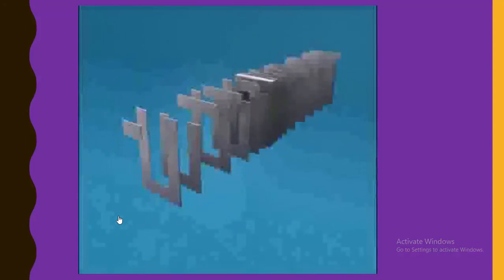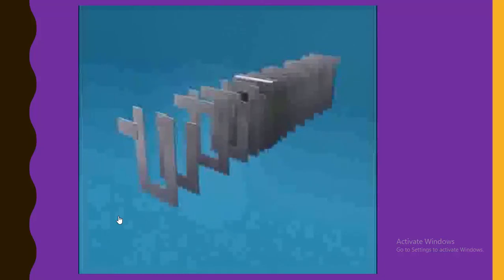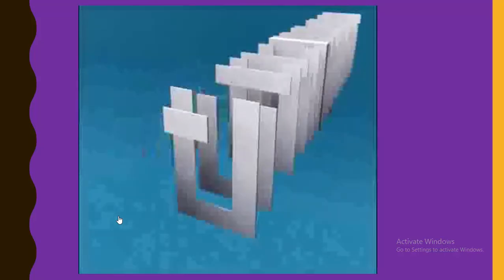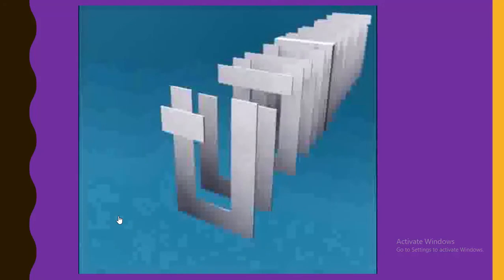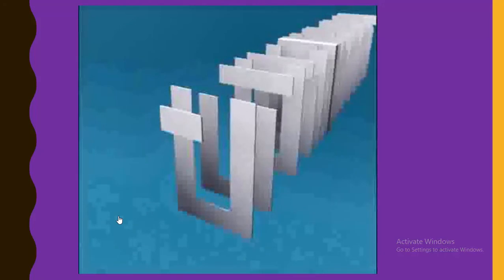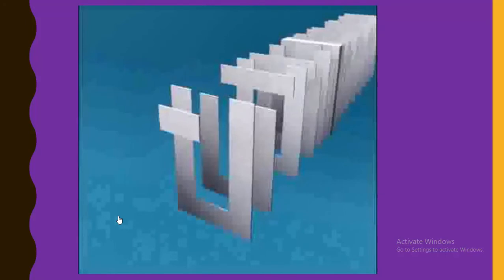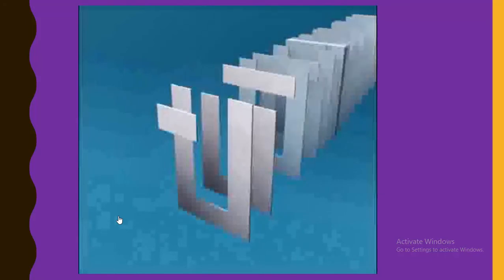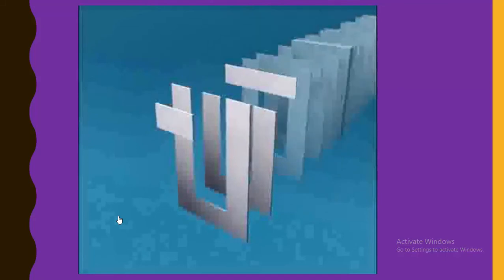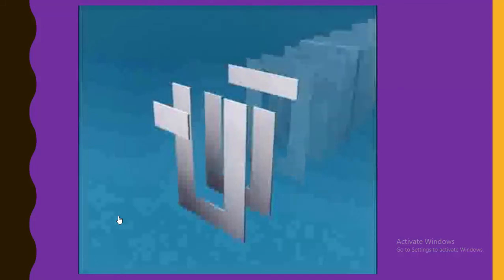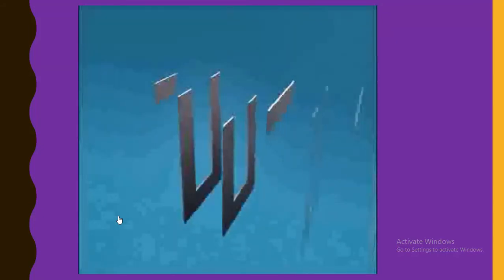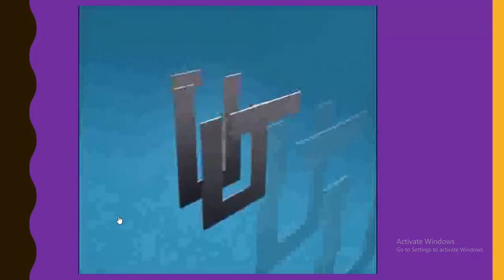This type of construction is used to reduce eddy current loss, which occurs inside the core when it carries changing or alternating flux. The core is used to provide a low reluctance path to the magnetic flux, but it is subjected to circulating electric currents. These circulating currents, called eddy currents, produce heating and energy losses within the core, resulting in decreased transformer efficiency.